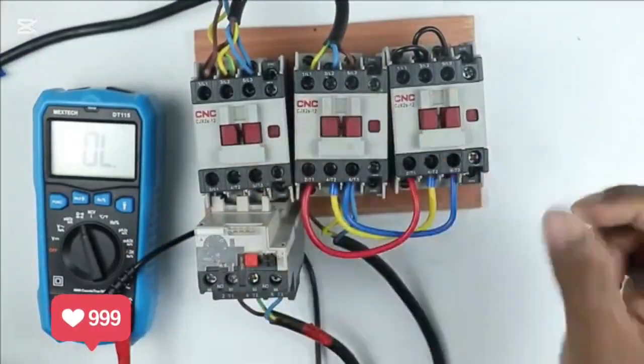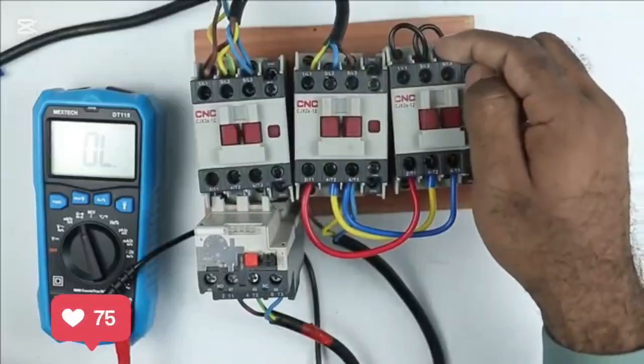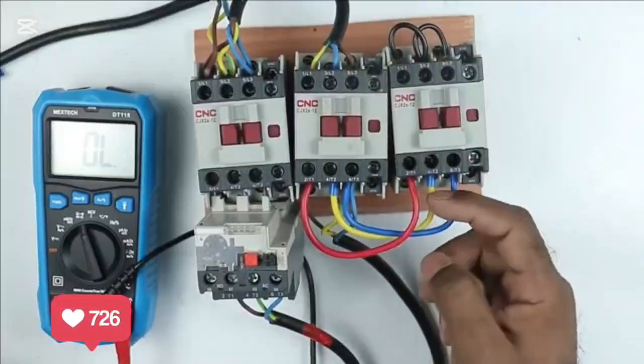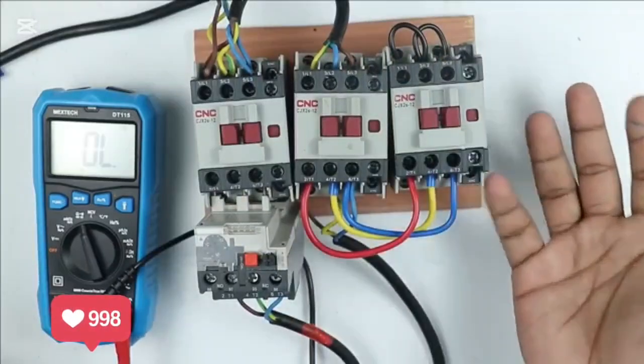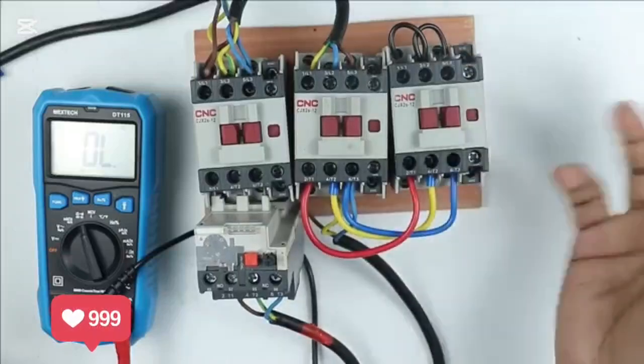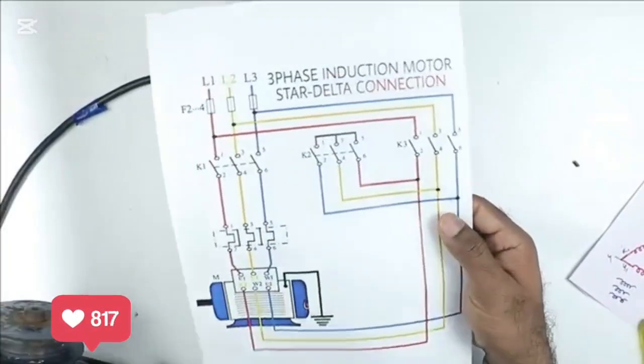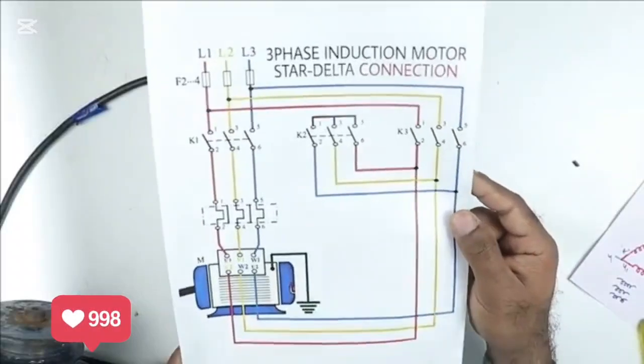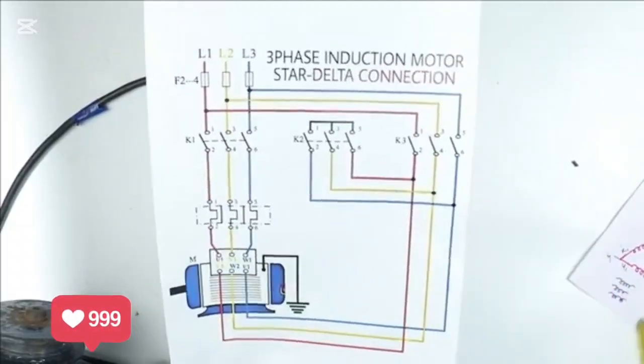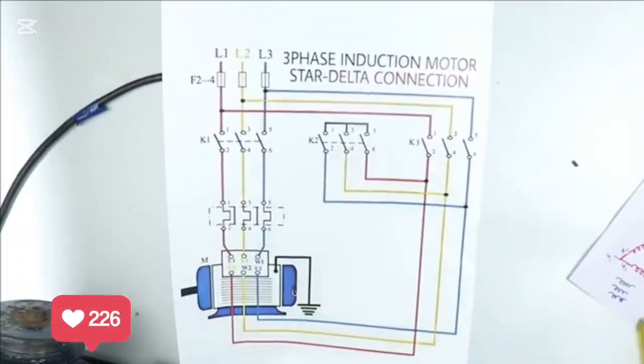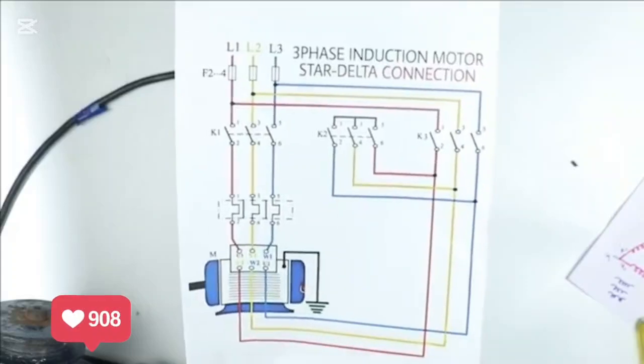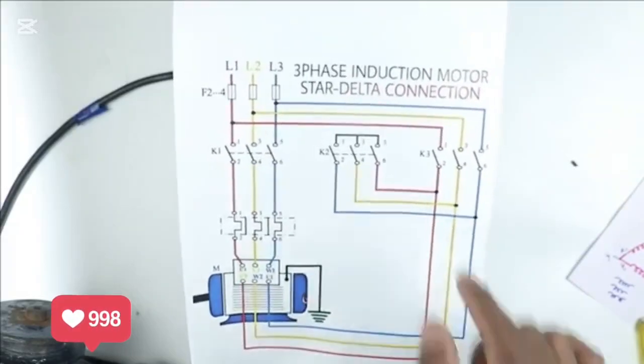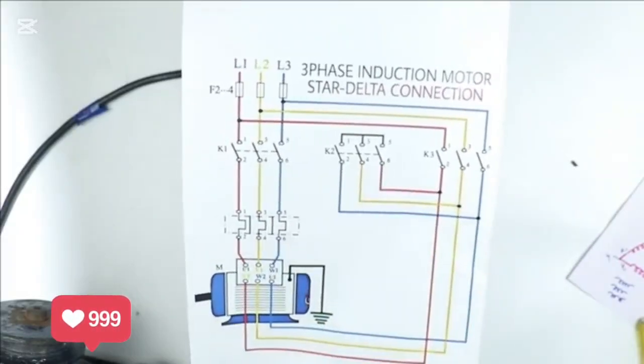We have to check this only. In star connection, wires above this are short, and below here you can connect any wire anywhere, it does not matter. So there is no need to check star connection. We only have to check delta connection. If you still didn't get the connections, then you can refer to this circuit diagram, then you will understand it completely. The wiring which I performed is same as this one. Only the color coding of wire is different here. It does not matter what color coding is, I explained you the whole concept.